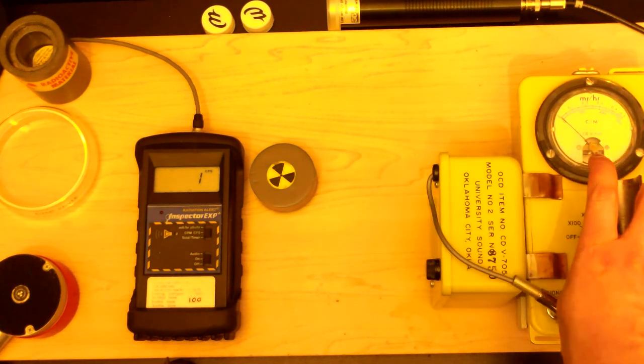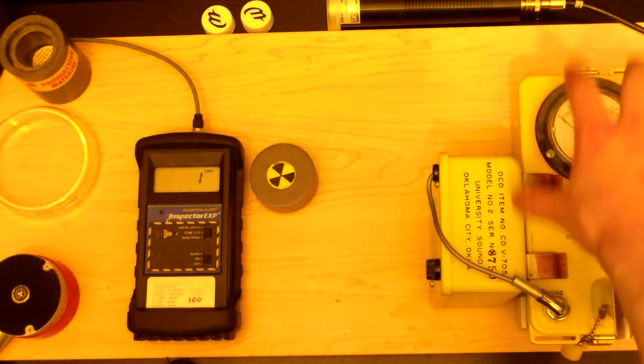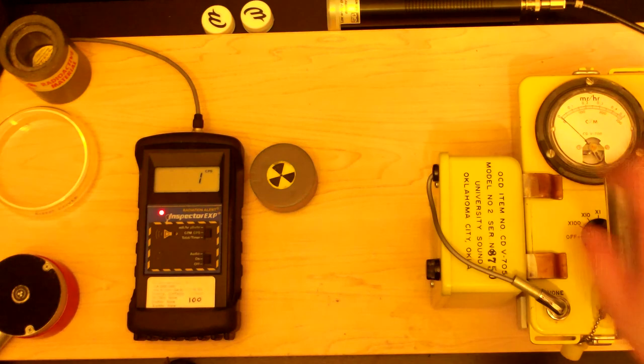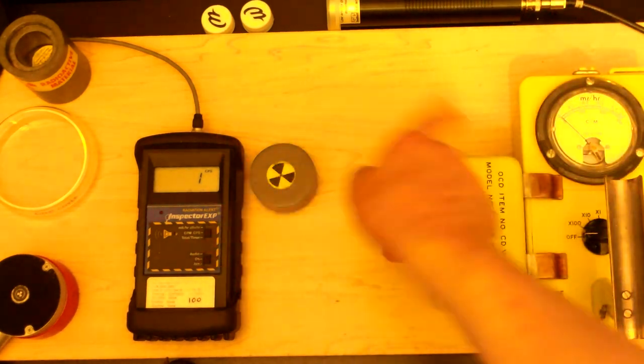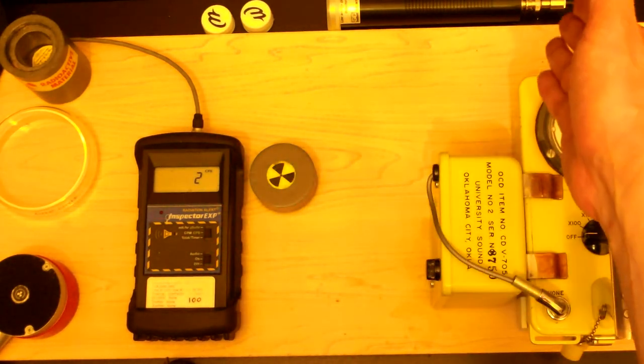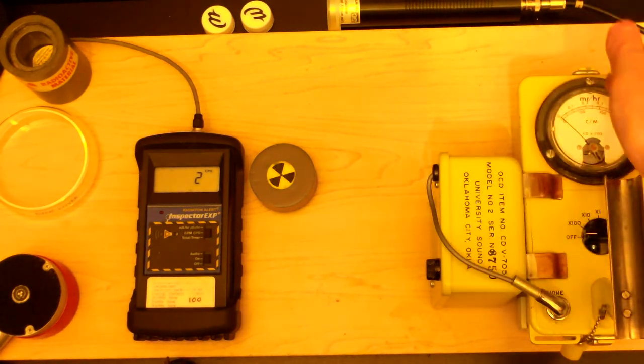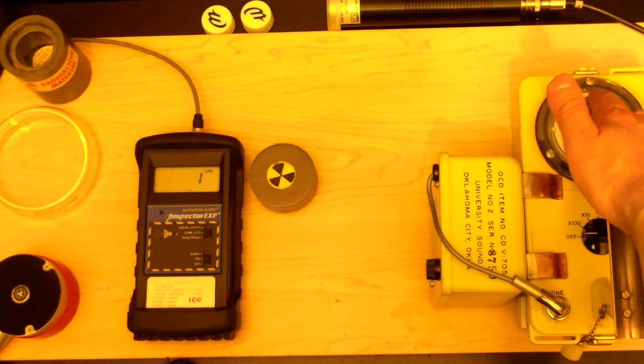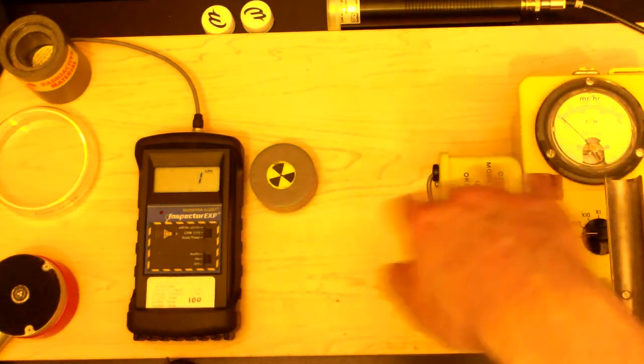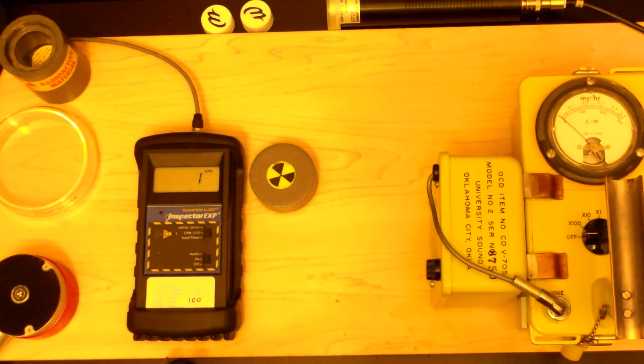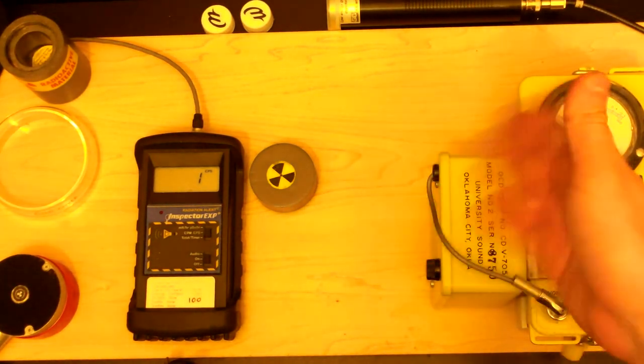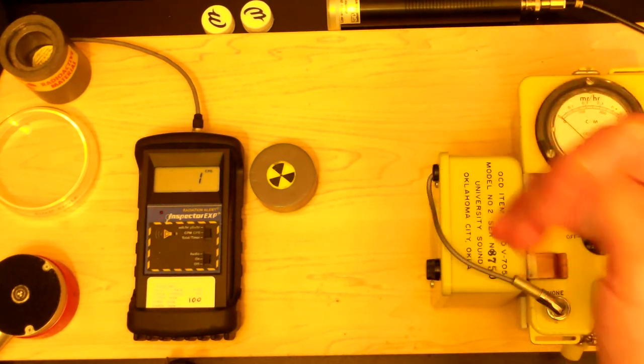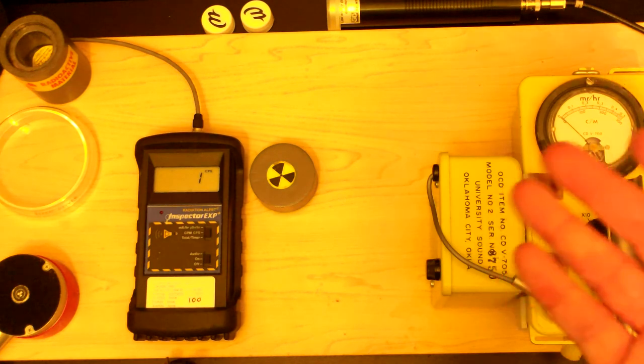More ticks, more radiation. Less ticks, less radiation. It's pretty simple. I mean, like a five-year-old could pretty much get the gist of how that's working, right? So this unit here will not tick as often as this unit here. And so I've heard a lot of people say, well, wait a second. Because these are both calibrated to Cs-137, their readings in energy units, such as millirem per hour or microsieverts per hour, they're going to match up probably because they're both calibrated with the same thing. And that's probably reasonably true. But there's a flaw in this premise. Just because they match up and just because it seems easier doesn't mean it's right.